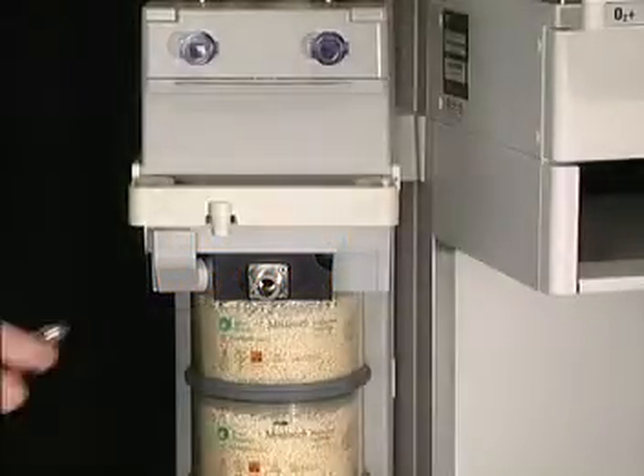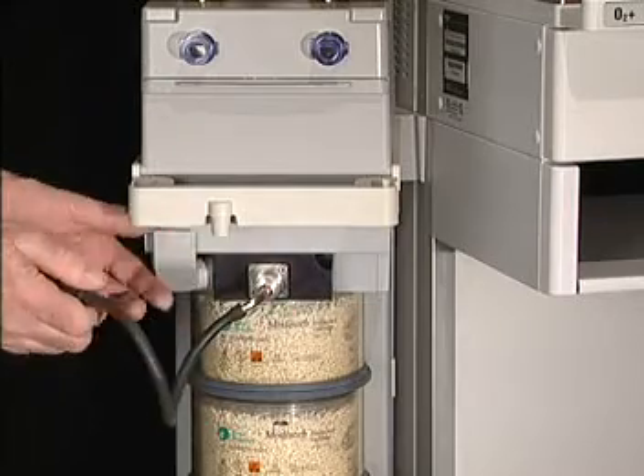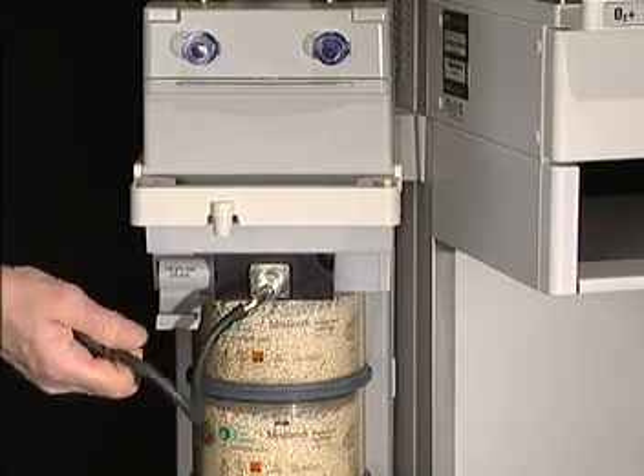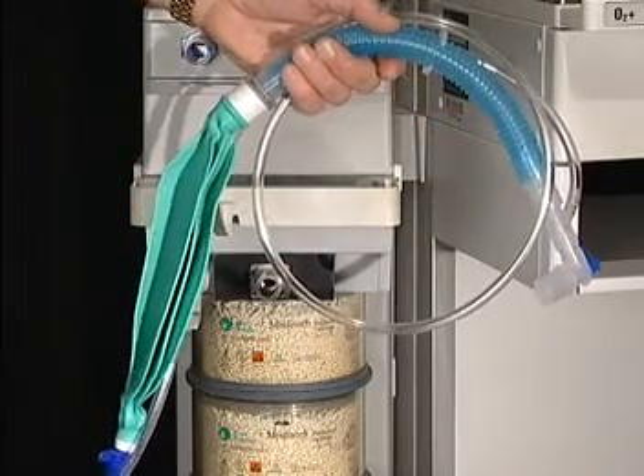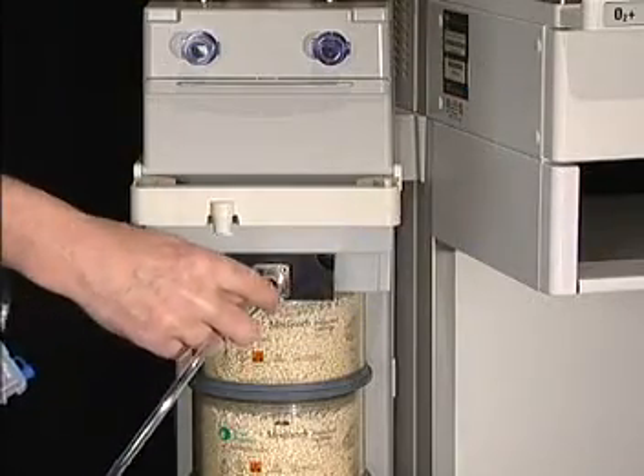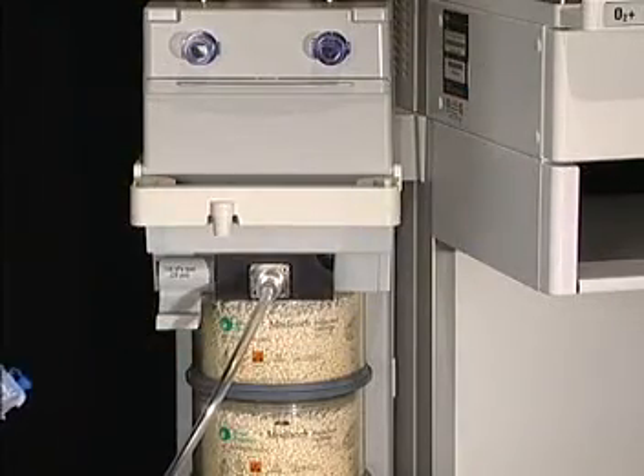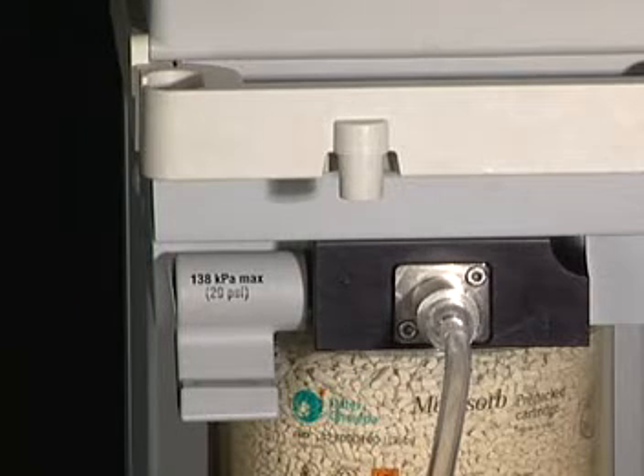The Estiva has an optional auxiliary common gas outlet. This outlet is an easy access port when conducting the negative pressure leak test and can be used for open circuits like a Jackson-Reese. Volume monitoring and mechanical ventilation are not available when the ACGO is activated. Fresh gas is available at pressures up to 20 psi to facilitate use of this port for transtracheal ventilation. It should be noted that there is a small bleed orifice from the auxiliary common gas outlet to the O2 sensor so that oxygen monitoring can be active.